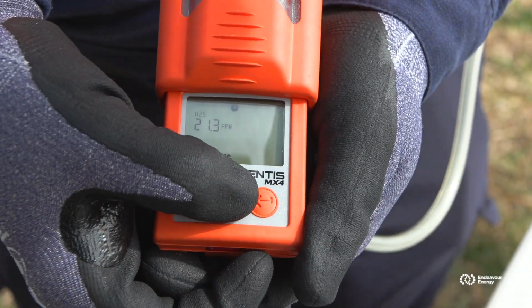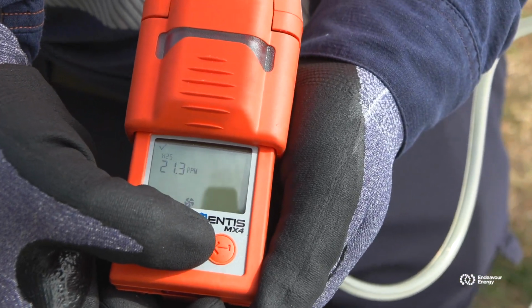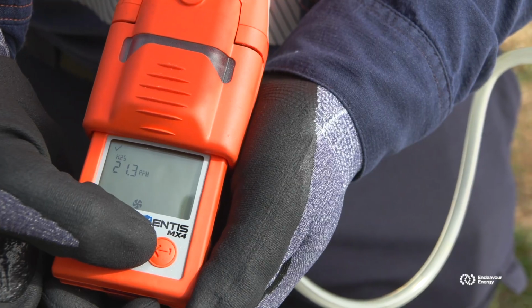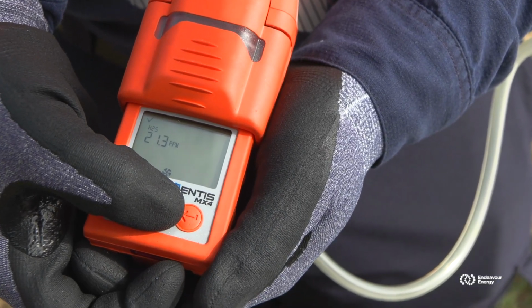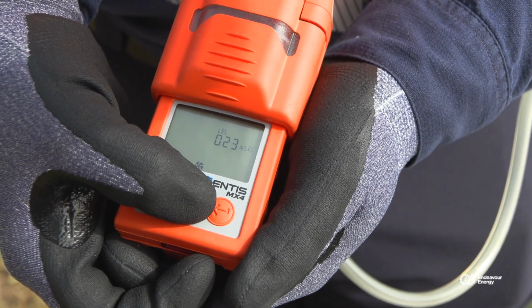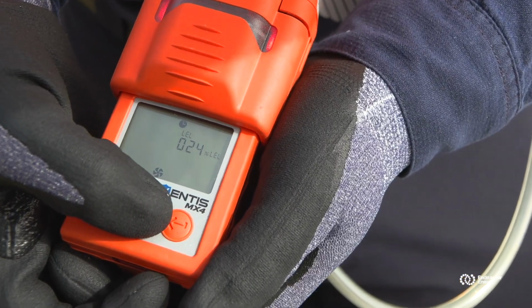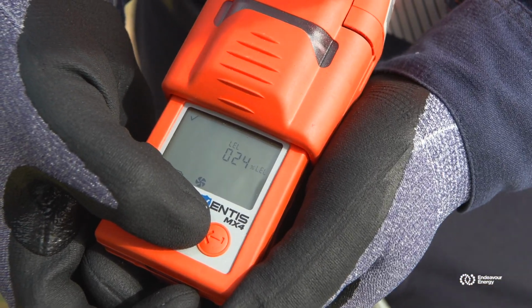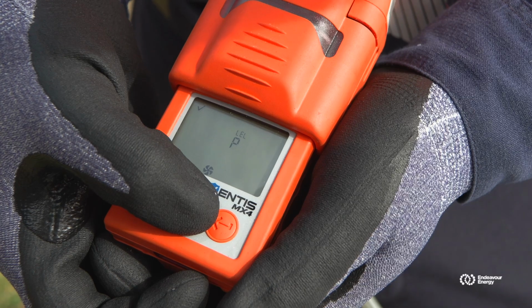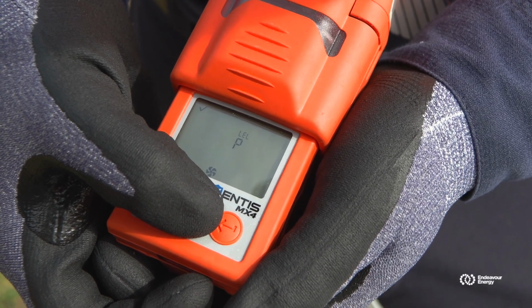If the speaker's a bit noisy, place your finger over the speaker in between the two buttons down here at the bottom, and you can watch as it displays on the screen each sensor, and it'll put up a P for pass or an F for fail. Currently, we're testing the lower explosive limit sensor, and it's displayed a P for pass.